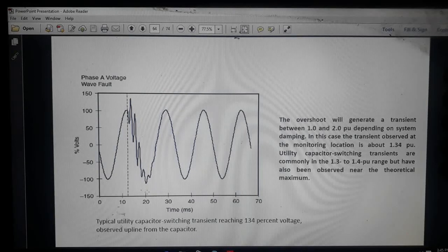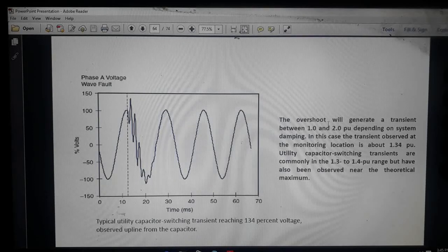This is the transient over voltage, and this type of fluctuation starts from here to around 20 milliseconds. The next cycle is a smooth cycle from 20 milliseconds to 70 milliseconds. The overshoot will generate a transient of 1.0 to 2 per unit depending on system damping. In the case observed, the transient at the monitoring location is about 1.34 per unit. Utility capacitor switching transients have been observed near the theoretical maximum.